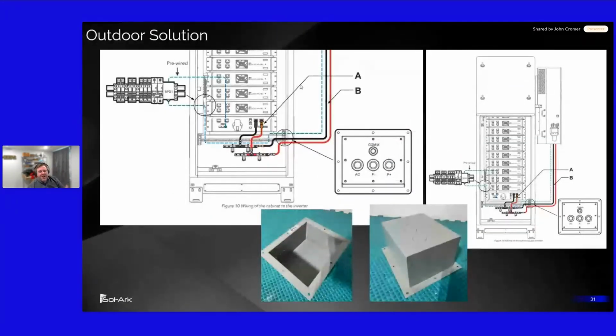So as you can see with our outdoor solution, at the bottom of the outdoor cabinet, we include a bus bar for combining up to 3 battery cabinets together, and that would go on inverter battery port 1, and then 3 more cabinets would go on battery port 2, and that would get you up to 6 battery cabinets per inverter. You transition out this little knockout box that comes off the side of the unit, so nothing terribly fancy.